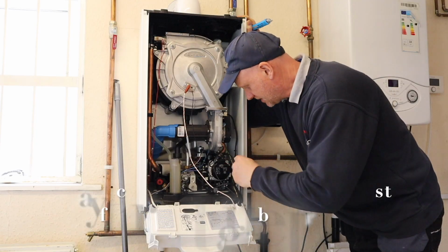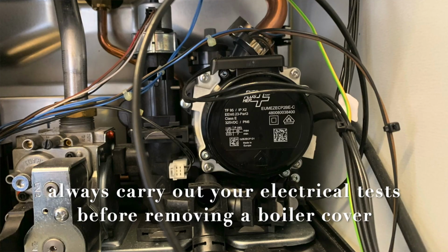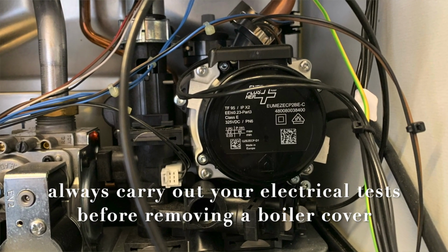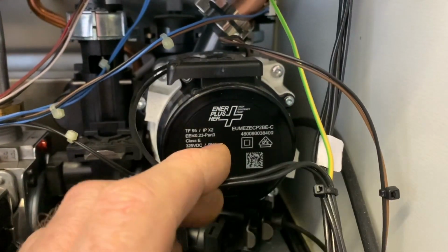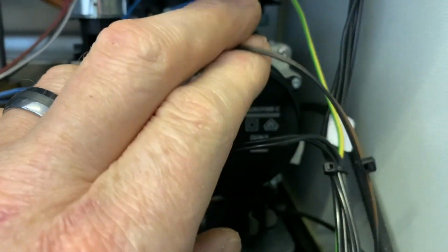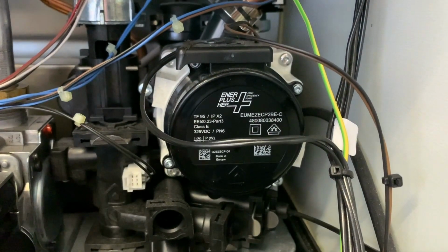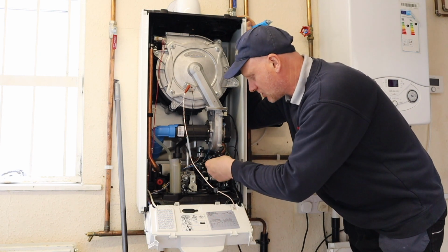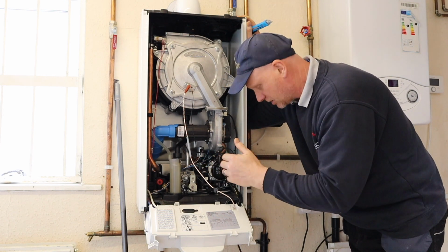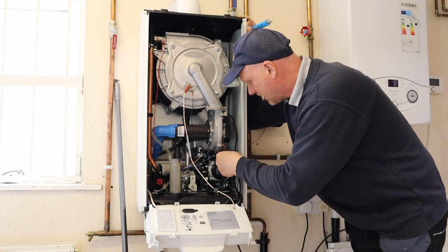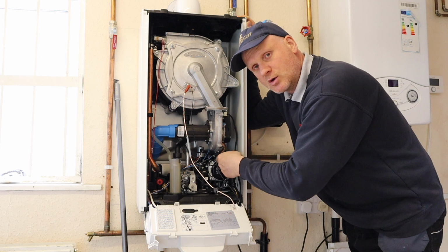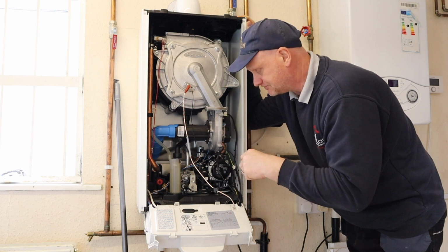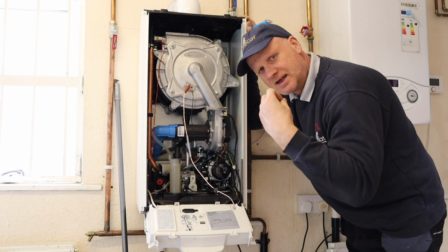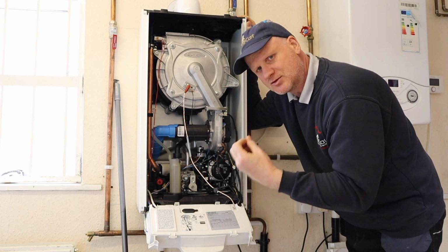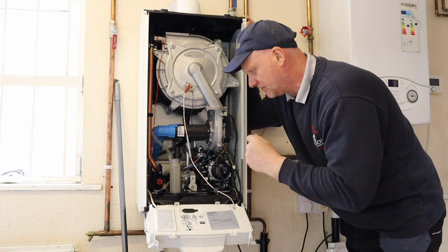Now this is the common sight now in a combi boiler that we've got this ERP pump. Now what we can see on the pump is we actually have two connections going to it now. So we've got two lots of wires. So we've got a low voltage side and we've got a 230 volt side. So we've got the 230 volt side to get it spinning, and then we've got the low voltage side now to modulate it. So modulation, basically what it's doing is it's slowing the pump down to try and keep the return temperature lower than 55 degrees.